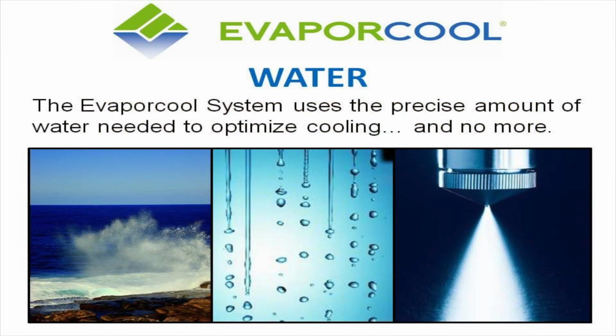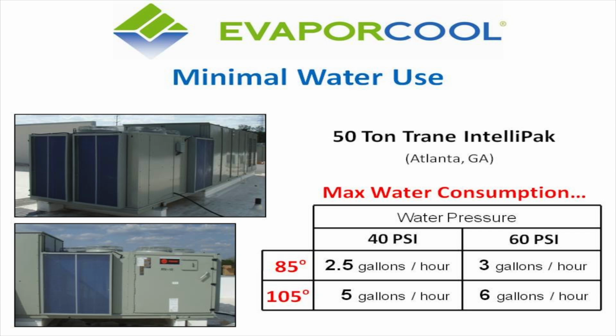There always is going to be a question about water, and yes, the system does require water, but there are two things to understand. One, the water is sprayed for a very minimal amount of time. It may be that the spraying goes on for 3 seconds or 2 seconds or 8 seconds, but it's not continual. It's based upon the temperature that's coming in. From a consumption standpoint, depending on water pressure, you're roughly looking at anywhere between 2.5 and 6 gallons an hour. It's not highly consumptive, and we continue to work on the efficiency of the water side as well.